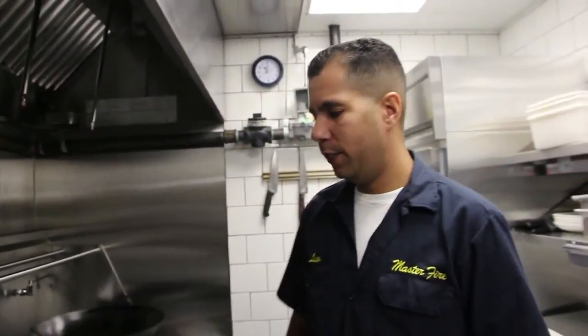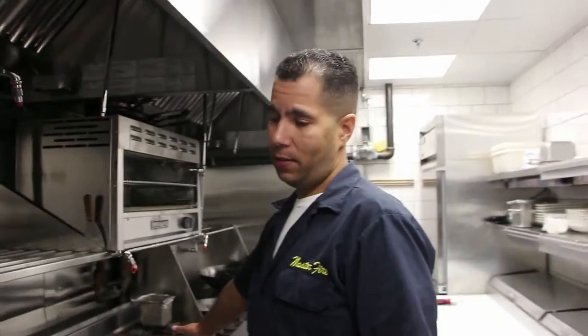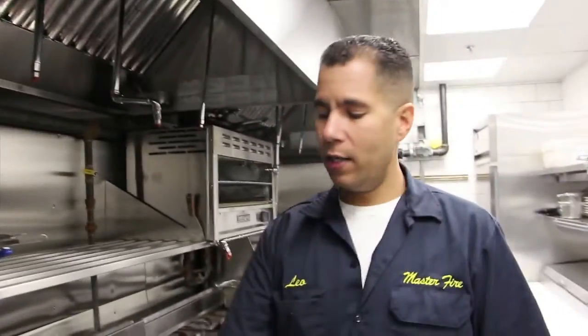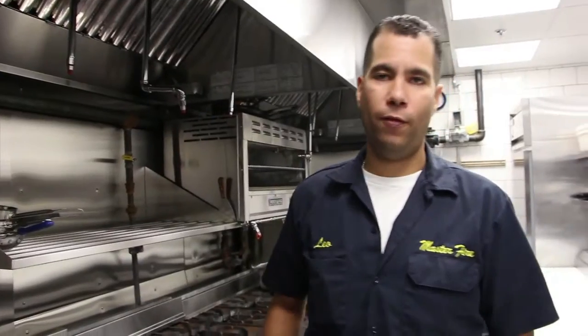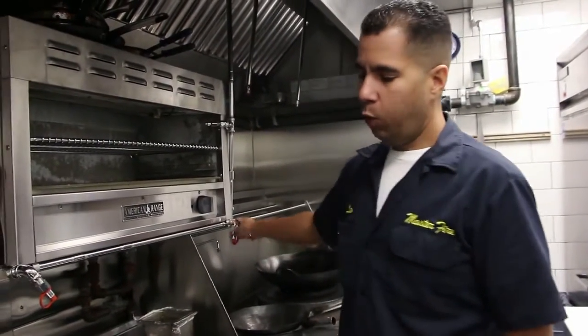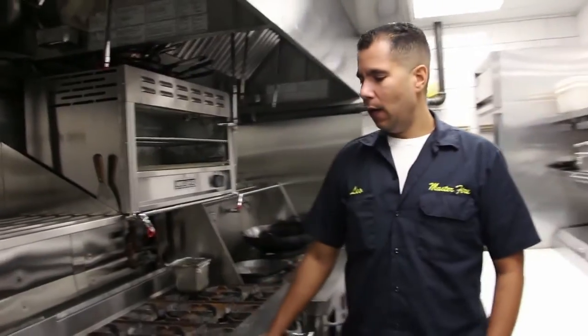There's different equipment in this kitchen. Here we have a six-burner range, a salamander, a set of woks, a flat grill next to that, a char grill, and a fat fryer. All this equipment requires a specific nozzle — they all have different hazards. That stove is a lot less hazardous than that fryer. This fryer requires me to not only extinguish the fire but cool off the oil — double the protection. Even though it's one nozzle, it's double the flow point. The six-burner stove, as you can see, has two nozzles — well protected. I also have a single nozzle over these two burners. Every single piece of equipment requires specific protection. They're all pre-engineered, and that's what we do — we make sure it's properly protected.